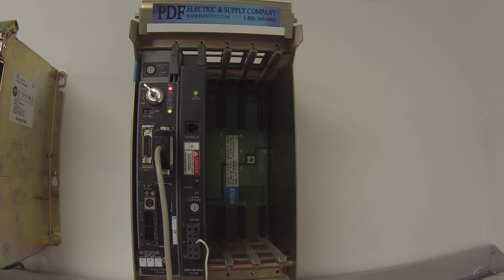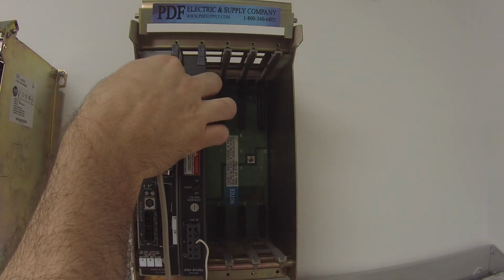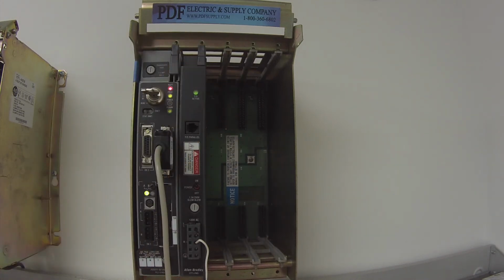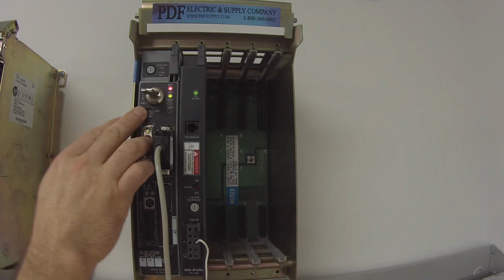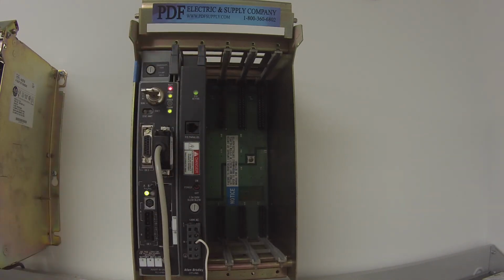Alright. So now that I'm online, where it used to say offline on the top left hand side of my screen, it now says program. So naturally what I'm going to do is turn this to remote program, hard run, back to remote run. For a test, you don't necessarily need the hard run, but you want to go all the way through and back to make sure that on your computer screen, on your software, it shows that you're green and in run mode and not faulted. So remote run is what I normally use to test this processor.